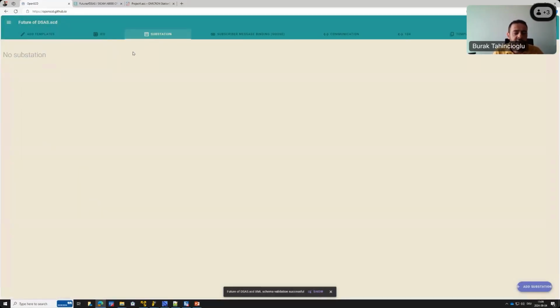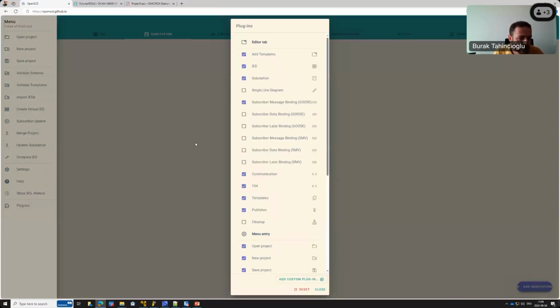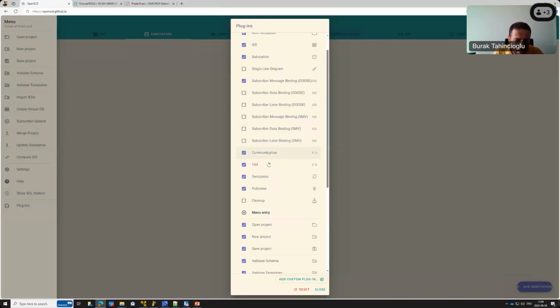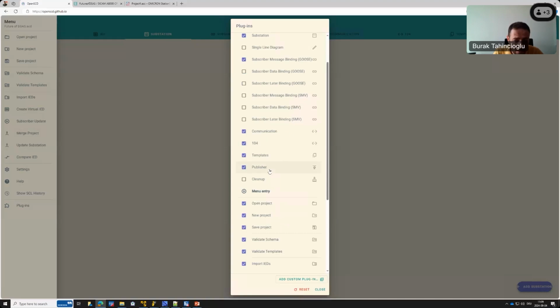OpenSCD consists of many plugins that can be used in parallel at the same time. On the left menu, you will see many plugins. What we will use today is the templates plugin and the IED substation plugin. We'll make one example with GOOSE and subscribe to this GOOSE, along with some communication structure. IEC 104 will be an interesting example to show you, because we will also add some data points into the SCL file - the 104 data points.